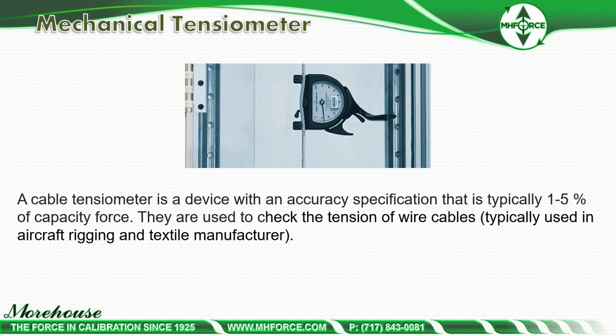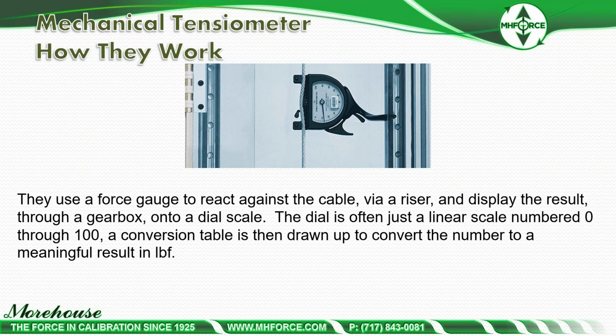But a cable tensiometer, for those that do not know, is a device with an accuracy specification that is typically 1 to 5% of capacity of force. They are used to check the tension of wire cables, typically used in aircraft rigging and textile manufacturing. They use a force gauge to react against the cable via a riser and display the result through a gearbox onto a dial scale. The dial is often just a linear scale numbered 0 through 100. A conversion table is then drawn up to convert the number to a meaningful result in LBF, KGF, Newton, whatever you're using.